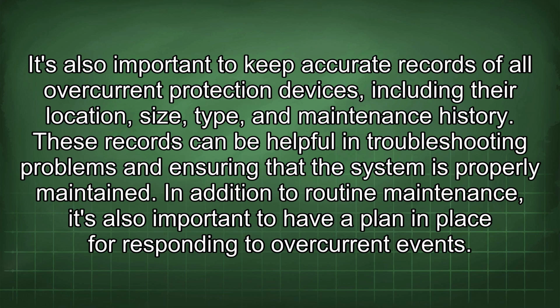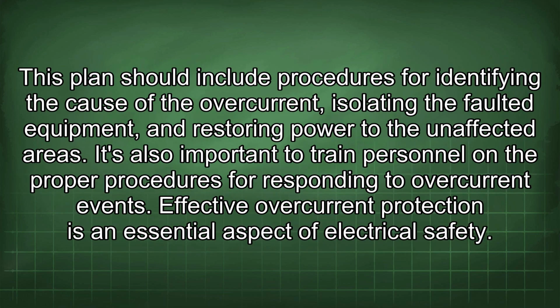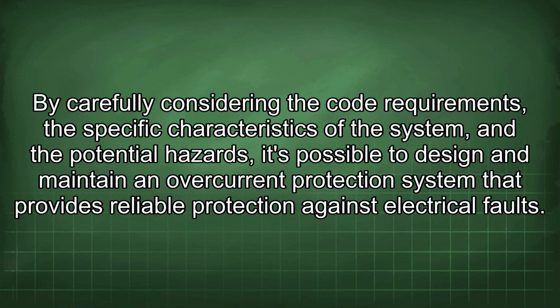In addition to routine maintenance, it's also important to have a plan in place for responding to overcurrent events. This plan should include procedures for identifying the cause of the overcurrent, isolating the faulted equipment, and restoring power to the unaffected areas. It's also important to train personnel on the proper procedures for responding to overcurrent events. Effective overcurrent protection is an essential aspect of electrical safety. By carefully considering the code requirements, the specific characteristics of the system, and the potential hazards, it's possible to design and maintain an overcurrent protection system that provides reliable protection against electrical faults.